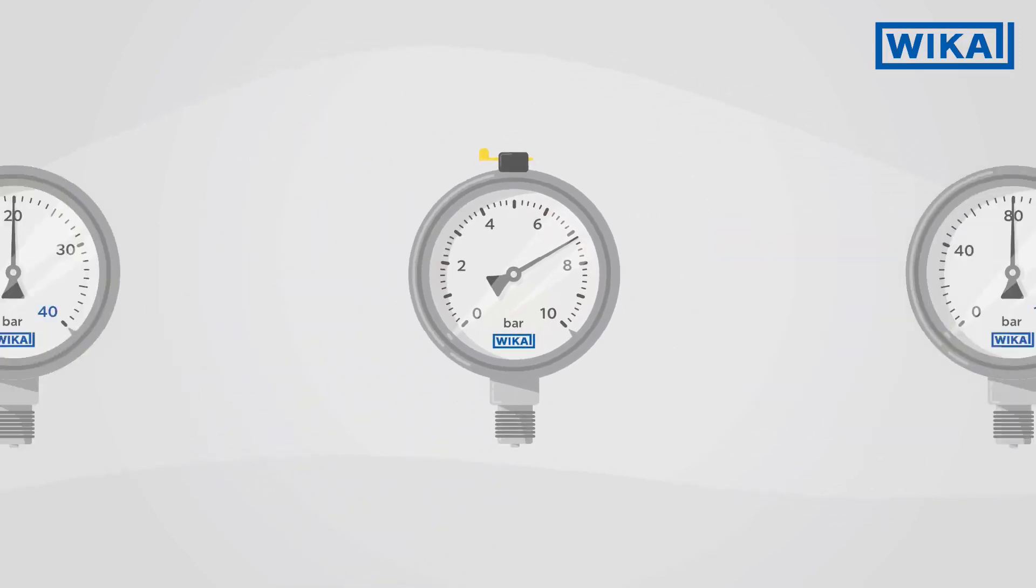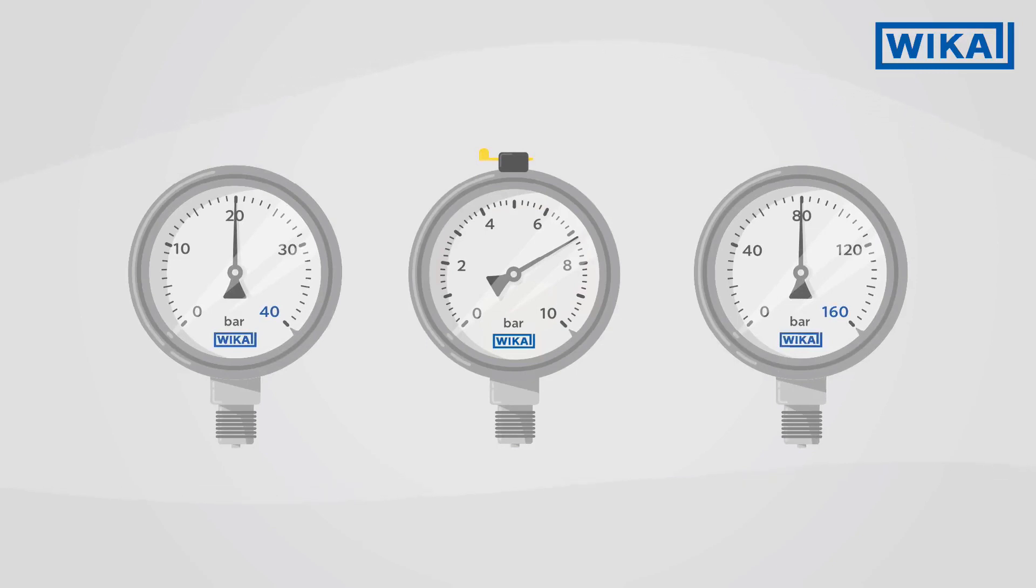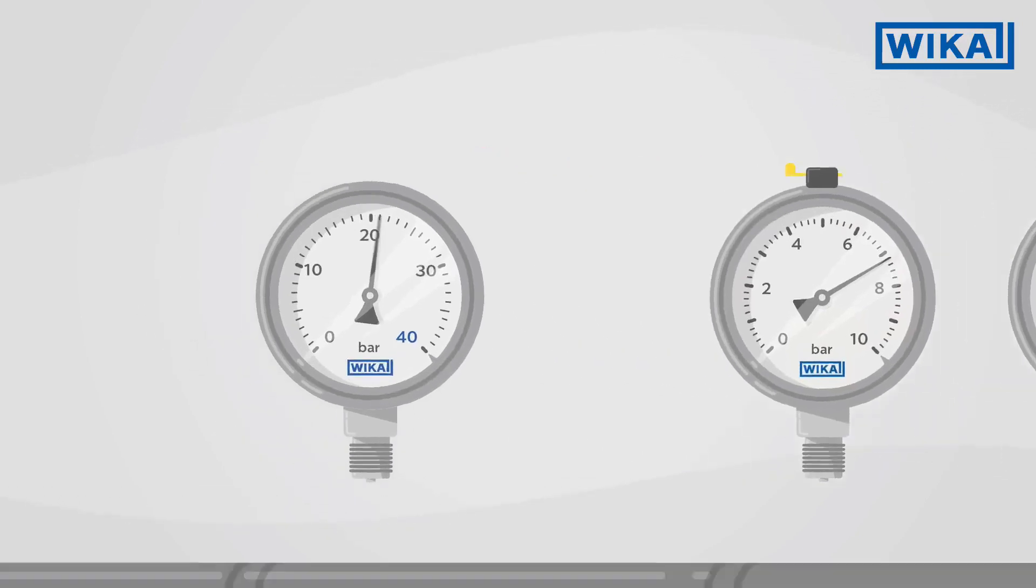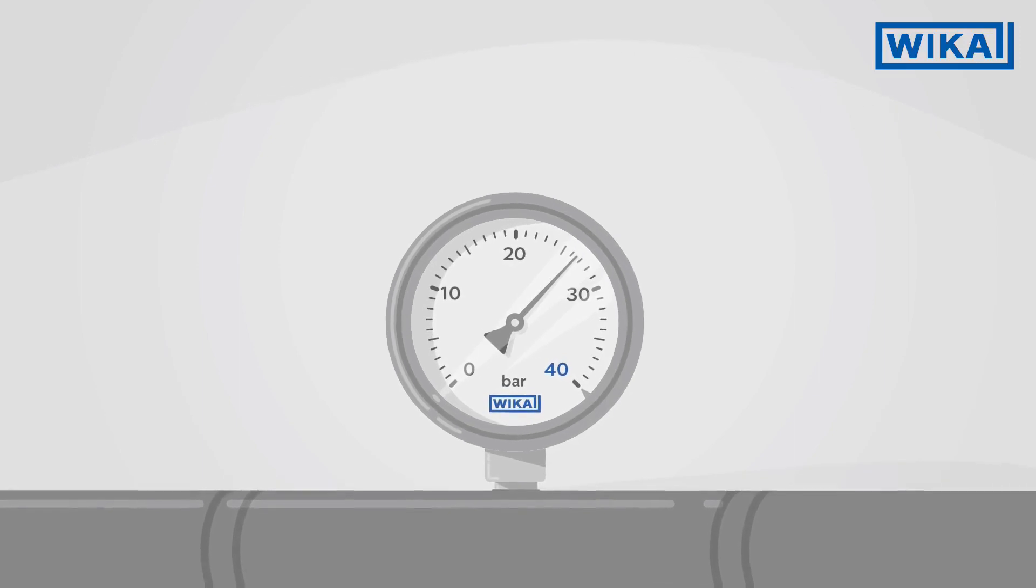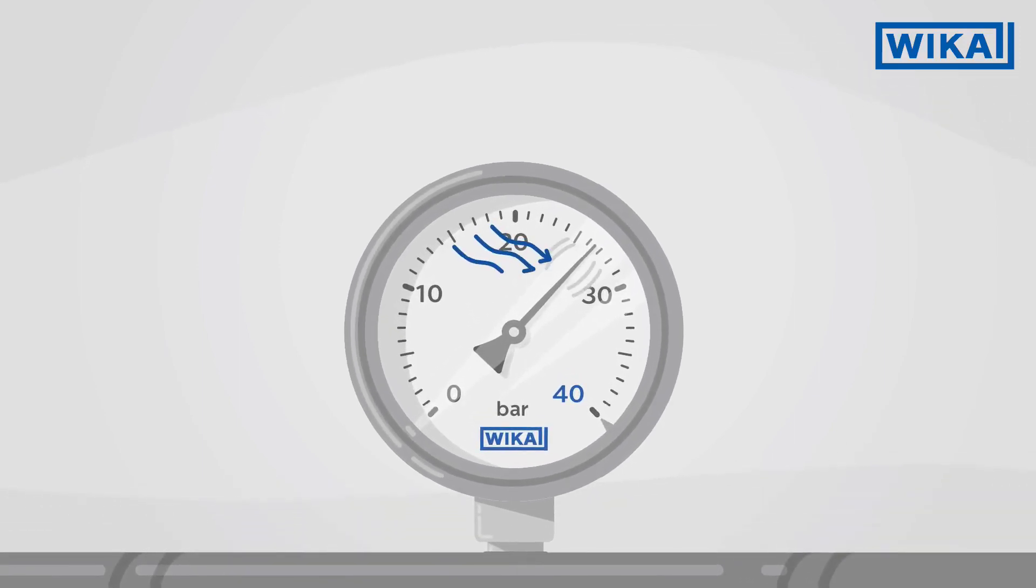However, not all WIKA pressure gauges have such a vent valve with this yellow lever. It is not needed for pressure gauges with pressure ranges over 16 bar. Here the temperature error can be ignored since it is so small in relation to the pressure range that the instrument will still operate within its specified class accuracy.